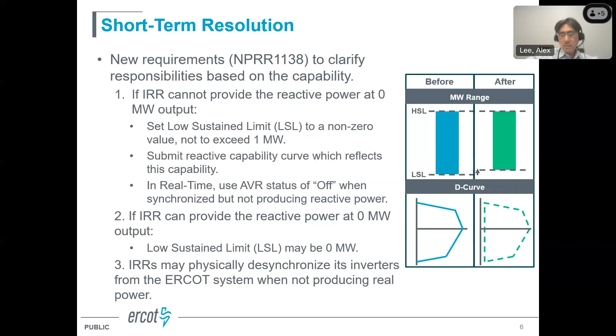On the lower right is how the D curve typically looked before this new requirement, where all the D curves started at 0 megawatts, showing both the leading and lagging capability. But with these new requirements, ERCOT requested or required resources to correctly reflect their capability, which basically ends up shifting the D curve to the right a little bit.